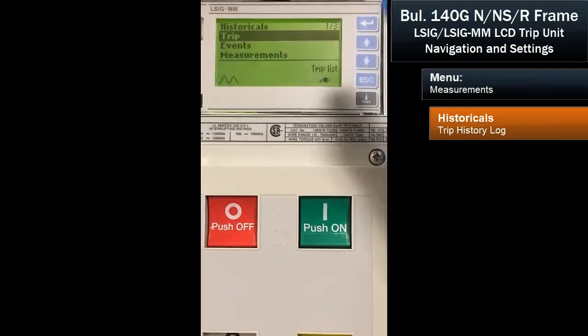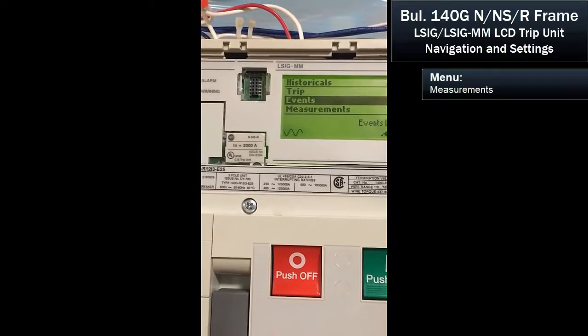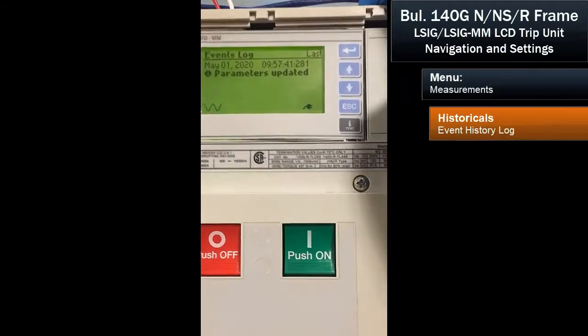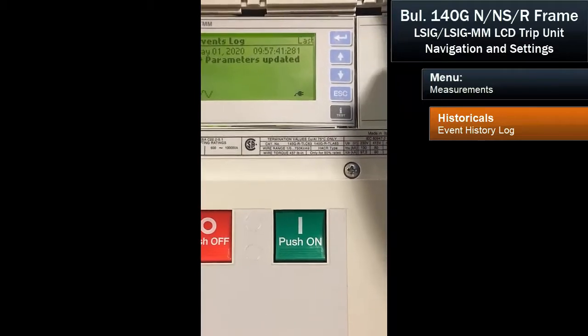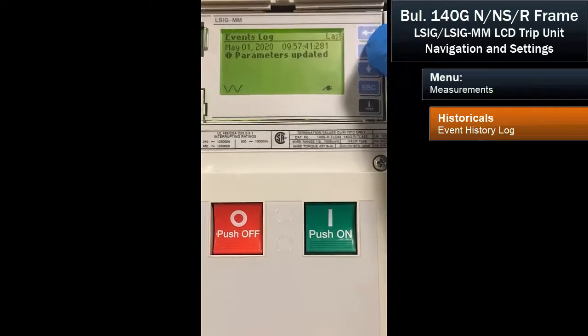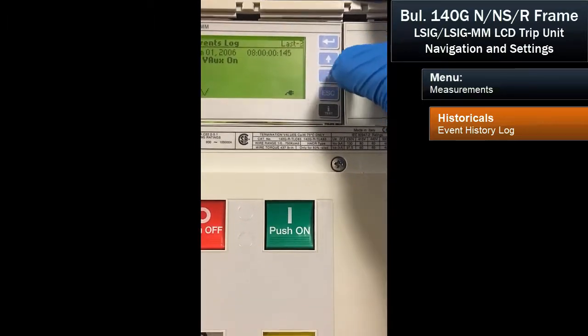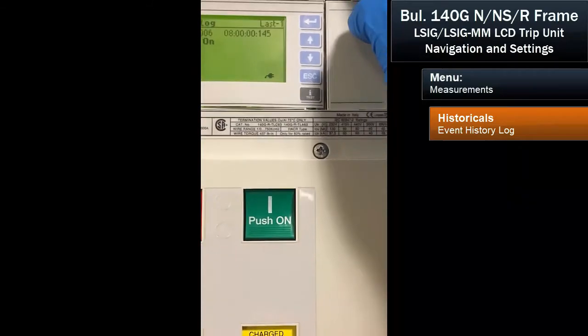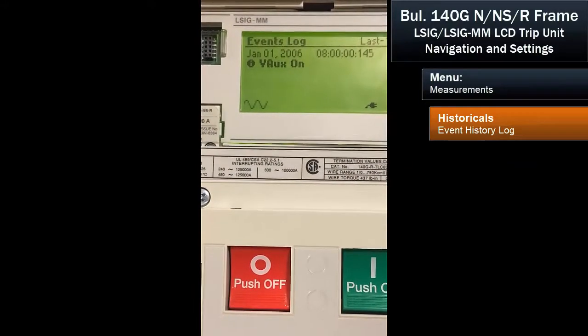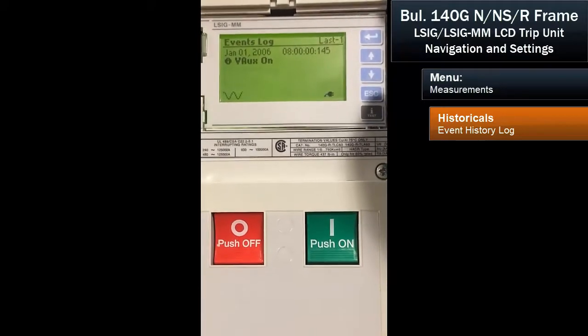We can escape and come back to the main menu. Now we can take a look at the events. In the event log, you can see that on May 1, 2020, we updated parameters. There were some other previous modifications made during demonstrations. The earlier dates are very close to the production date — those parameters were likely programmed during factory testing of the device.